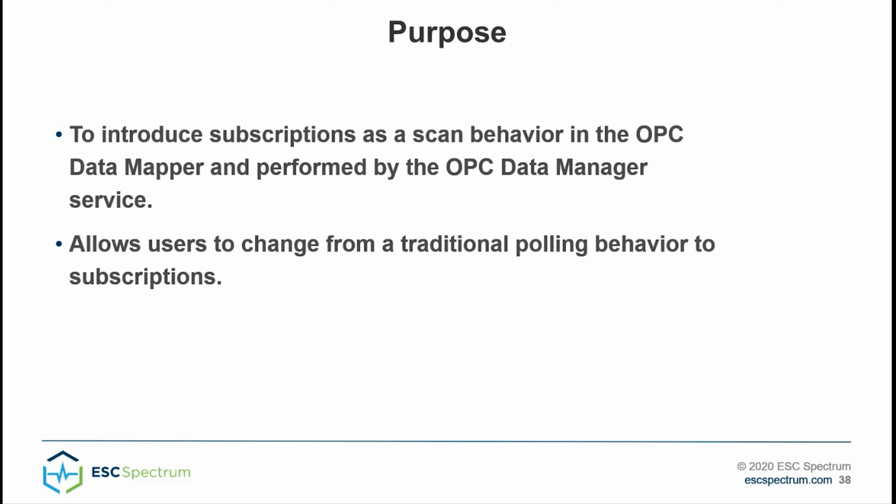For environmental compliance, we have to have data every so often to create valid intervals, so it might not make sense. In fact, the default is still going to be that traditional polling type, every once a minute or whatever. But for certain cases where subscriptions make sense, subscriptions are really the preferred OPC UA way of getting data. It's the preferred polling method, so we should at least have that as an option.